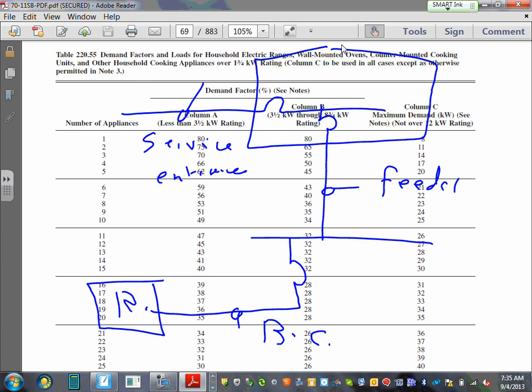Every time there's a load calculation that you need to do, you have to ask yourself, are they talking about service entrance conductor sizing, or feeders, or branch circuits? Can I just get you to understand that one from the get-go? Because if you don't, you don't know where to use the calculation that we're going to be using now. The calculation that we're going to be using right now is for service as well as for feeders. So this table is going to be sizing the service conductors here as well as the feeders.